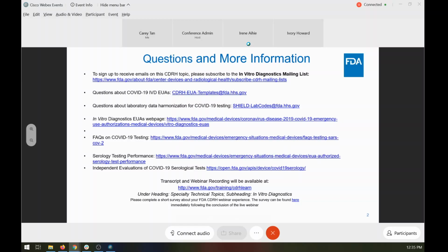And I can also note that we do have some information on our FAQ page about alternate testing supplies. So, for example, we talk about the different types of swab types that can be used. Most tests now that are being authorized are for use with all of those: NP swabs, OP, mid-turbinate, and anterior nares. So we do talk about that. If you wanted to add a new specimen type altogether, like adding saliva, that would be something that you would come back in with. These questions, or my responses rather, are all presuming that you're talking about a distributed test kit. So those are all the different considerations that you would want to look at, is sort of, what you want to be able to include in your original instructions for use and what you might want to add later.